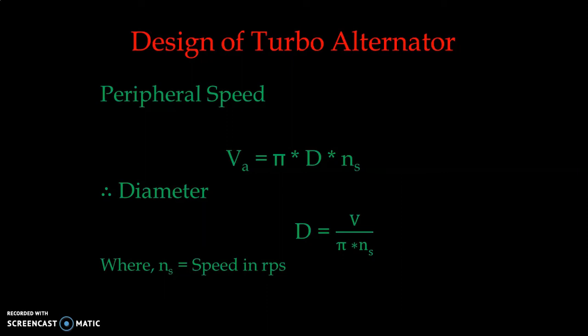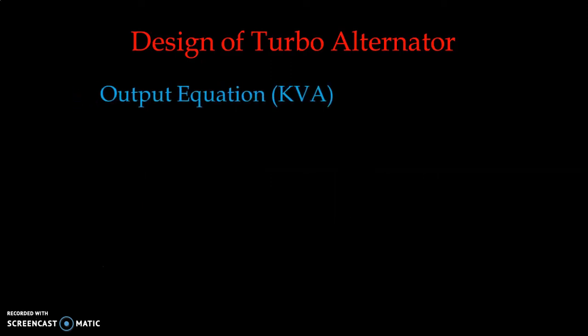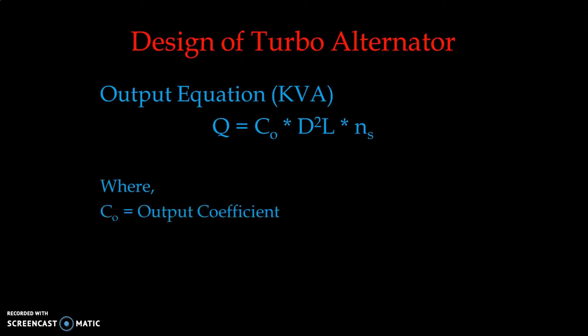Based on this diameter, if we substitute this value into the output equation, then the length of the stator core can be easily estimated. The output equation, normally in KVA, is Q = CO × D² × L × Ns. D and L are the main dimensions — D is the diameter of the stator bore and L is the length of the stator core. Ns is speed in revolutions per second, and CO is the output coefficient. CO can be expressed as 1.11 × π² × Bav × Ac × Kw × 10⁻³.